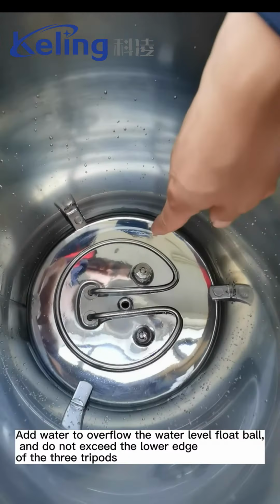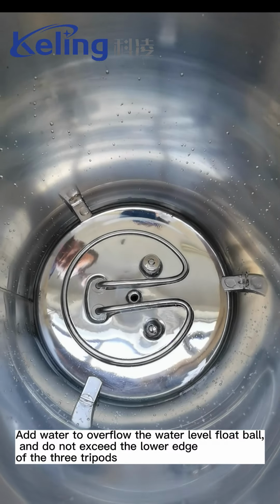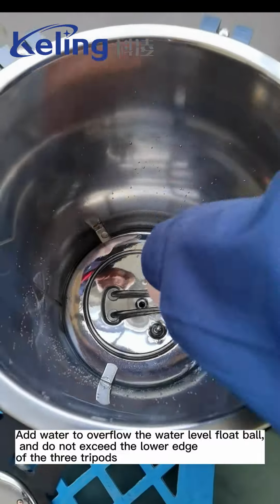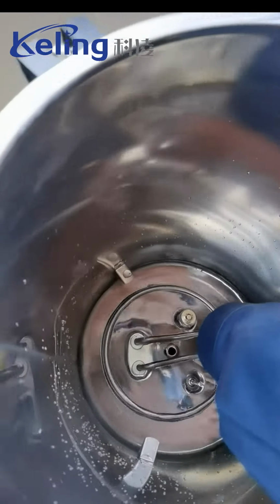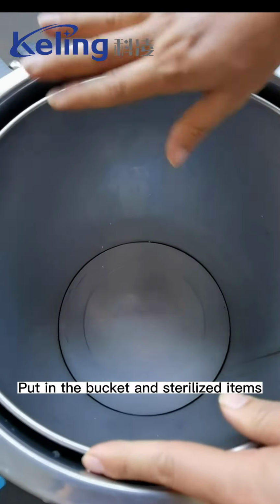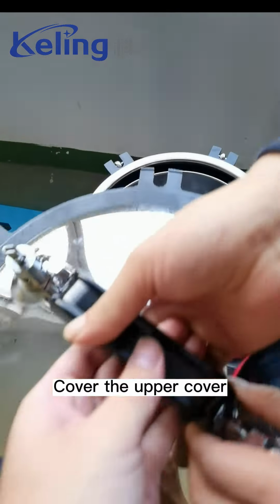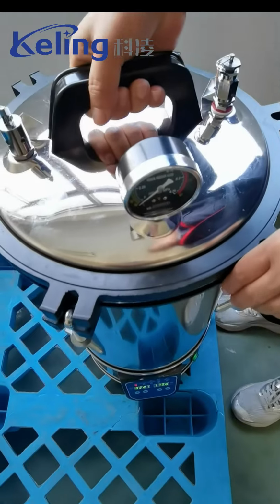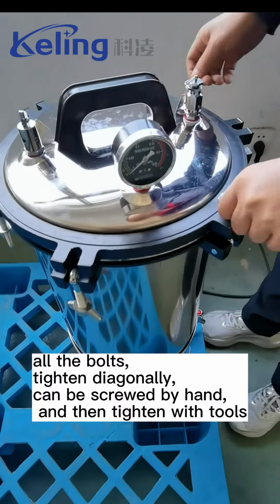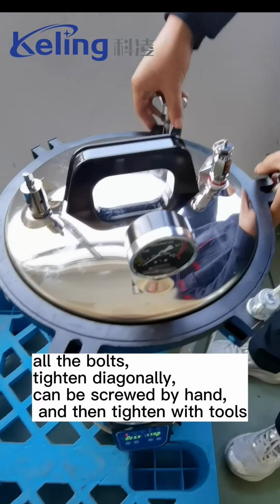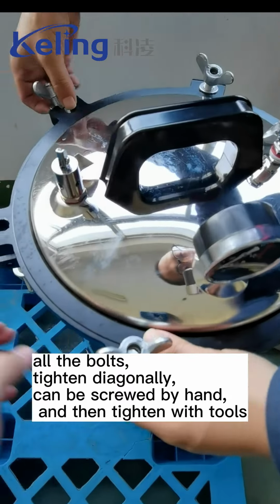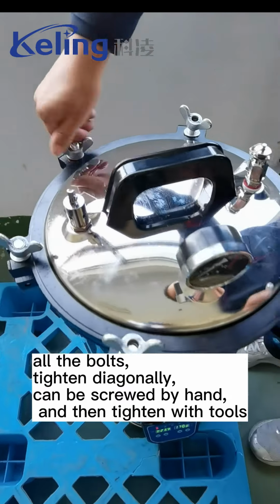Add water until it overflows the water level float ball, but do not exceed the lower edge of the 3 tripods. Put in the bucket and the items to be sterilized. Cover the upper cover. Tighten all the bolts diagonally; they can be screwed by hand first, and then tightened with tools.